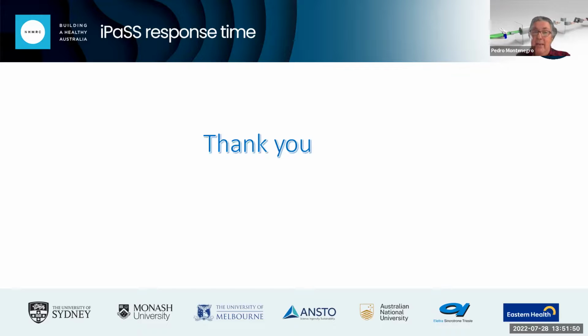And we had a 2% difference in integrated dose between the 2 scans, which were conducted 1 week apart. So that was for us a major milestone, and it augurs well for the pre-operational testing that we have to start in October to get all the safety data we need to send to ARPANSA to get the permission to image patients. And that's the end of my presentation.